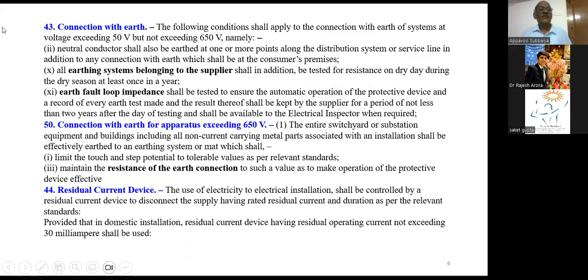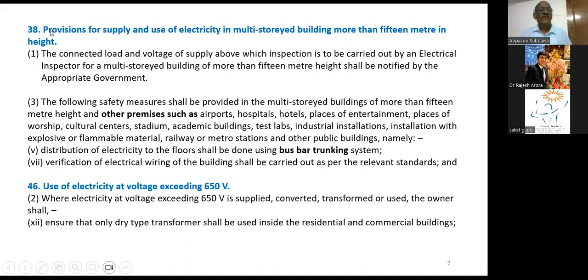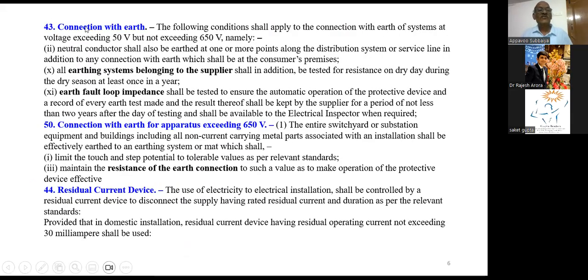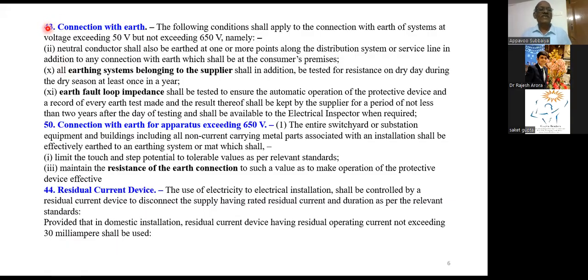So this is another thing. Regulation 43 says about the connection with the earth. This is the thing that has been revised. After the 2023 regulations, it has done a wonderful job. The majority of the confusions that occurred in the previous 2020 and earlier rules have now been eliminated. You can see from 43, this is the connection with the earth.